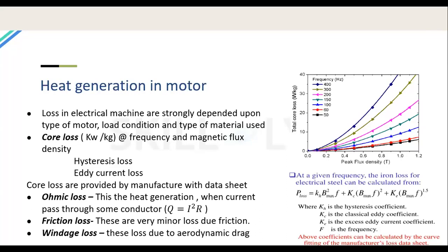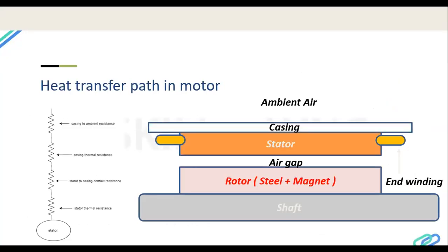To avoid eddy current losses, motors are built with lamination stacks of steel material with very small thickness — typically 0.35 mm. Reducing the lamination thickness reduces eddy current losses. This is why motors are never solid blocks — they are made of stacks to reduce eddy current losses.